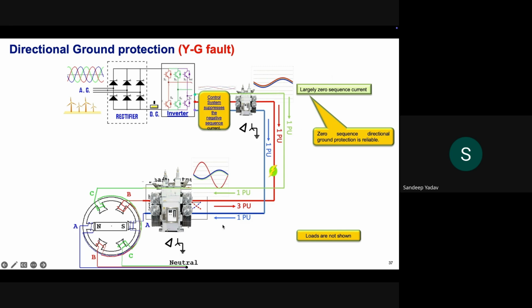However, on the conventional source side, we have all three components in place: positive, negative, and zero sequence, right? Because the controller plays a very big role in defining what would be the fault current behavior, and because the legacy systems or the old systems do not support injection of negative sequence current, the fault response is very different from a conventional source, both in case of a single phase to ground fault as well as in case of phase-to-phase faults.